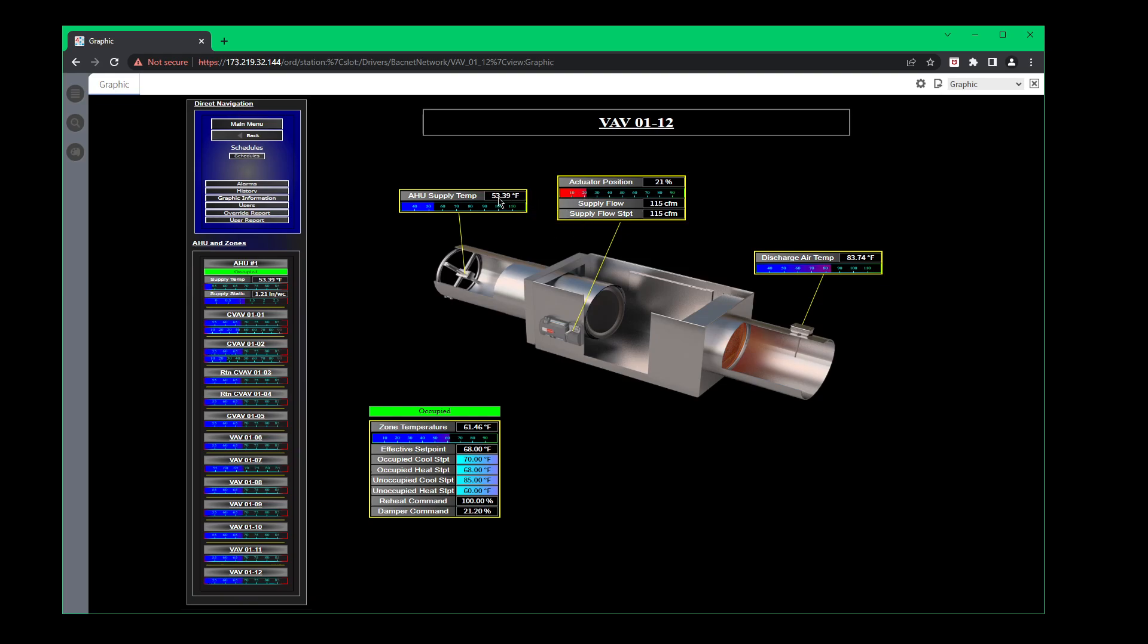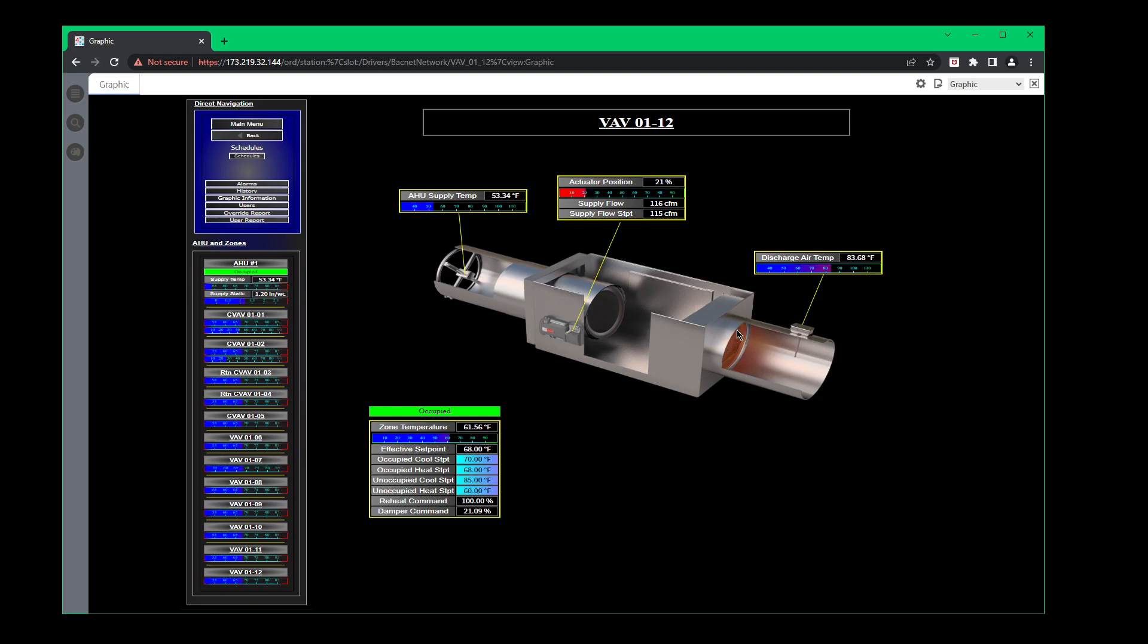Now we can do a reset on the air handler based on space temperature or outside air to actually make your heat kits a little more efficient. One of the issues is, when it's cold outside, you don't necessarily need it to be 55 degrees. But then you also have the operating room that you have to try to maintain. So you want to look at this, then you want to look at your actuator position. The fact that these boxes are VAVs and not fan powered, they are going to require air flow from the air handler to run across the heat strips to get proper air movement and your heating into your space.